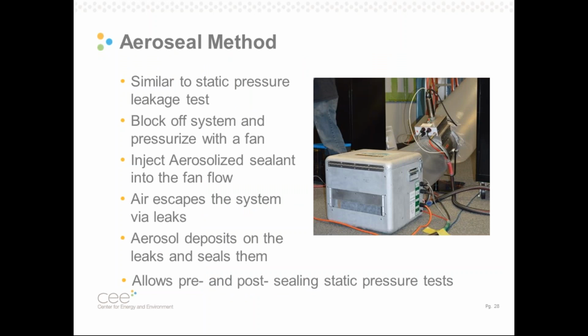Then we've got this other method for retrofit duct sealing, which is based on a whole other premise. And actually, it's a lot like static pressure testing. This is an aerosol-based process made by the Aeroseal company that they have patented and license out to individual contractors. But like a static pressure test, this sealing technology requires that you turn off an air handler and block off a section of the duct system. That includes the inlets and the outlets.